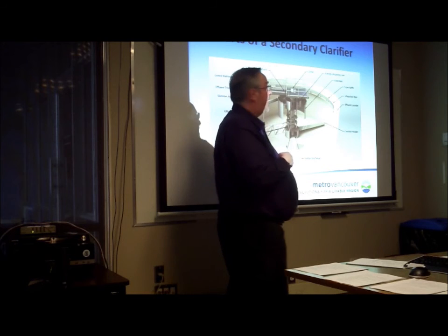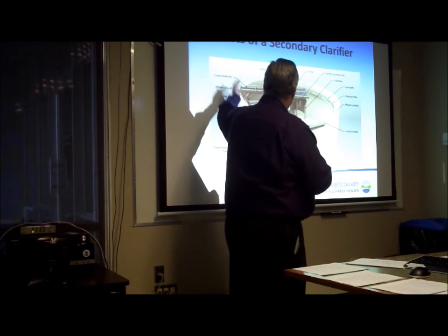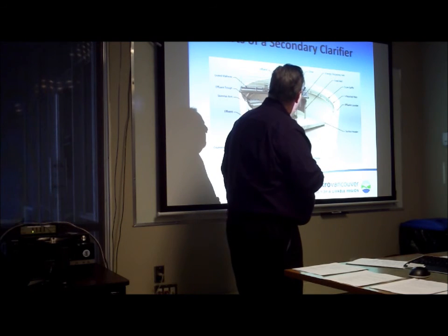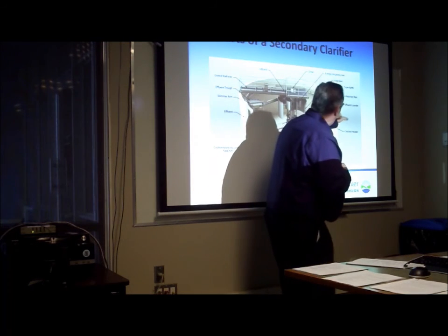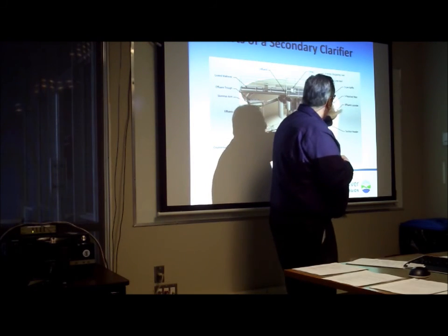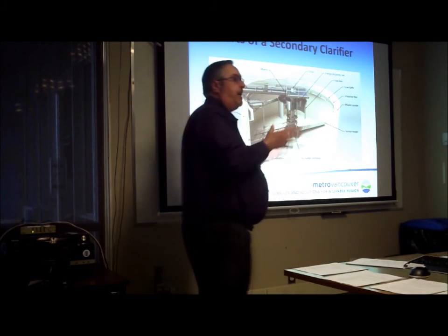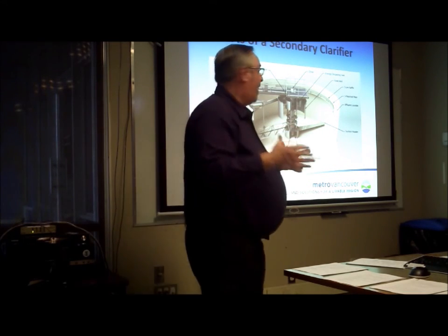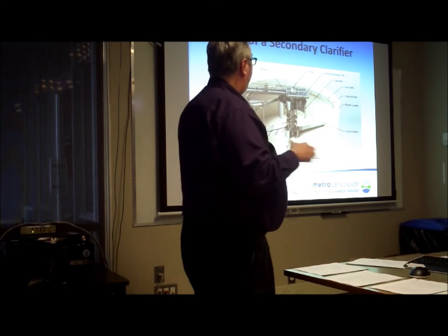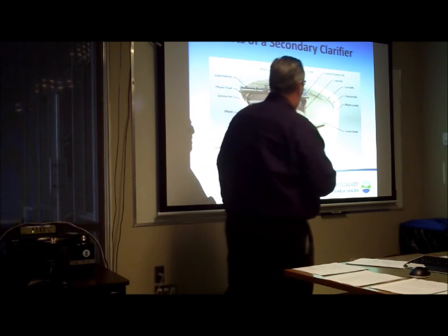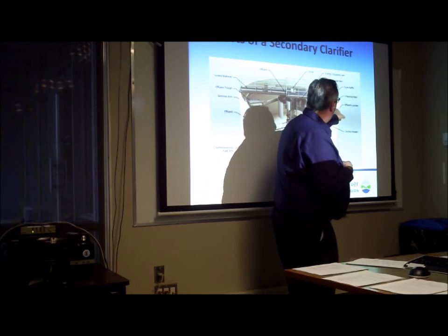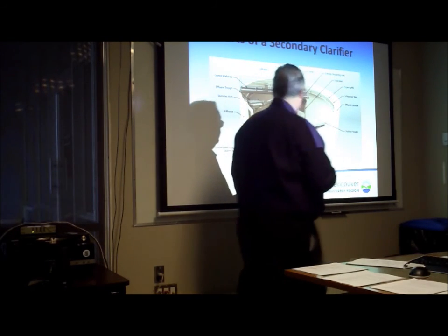Obviously, most clarifiers have a catwalk, grated walkway, as they call it here. The drive motor, there's a scum baffle here. It doesn't show it very well, but you can see there's a V-notched weir, and the scum baffle just contains any pin floc or possibly minor bulking sludge. And this trough here, just like we have on our thickeners, is an effluent launder.